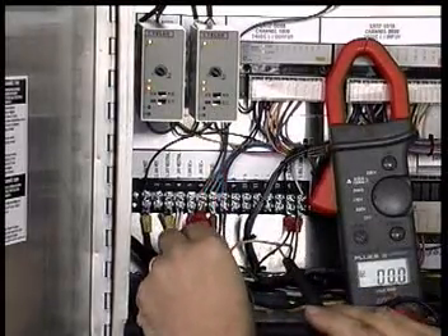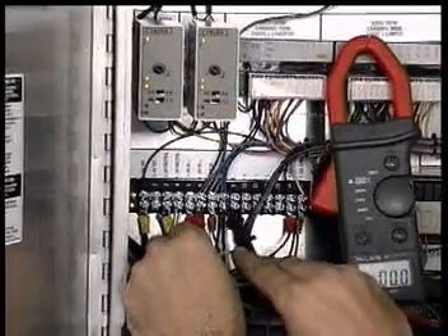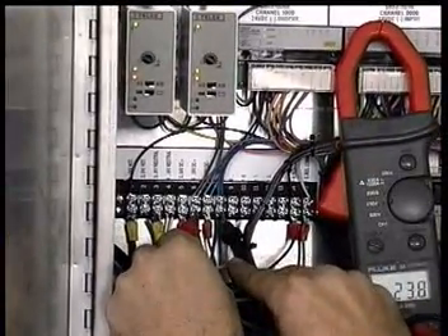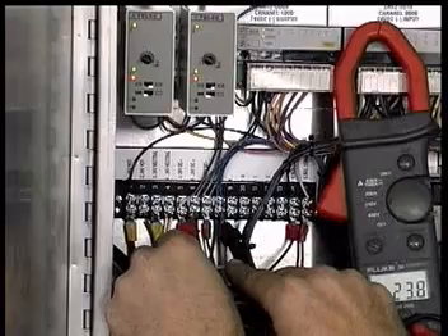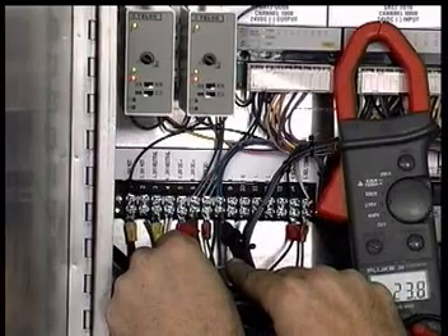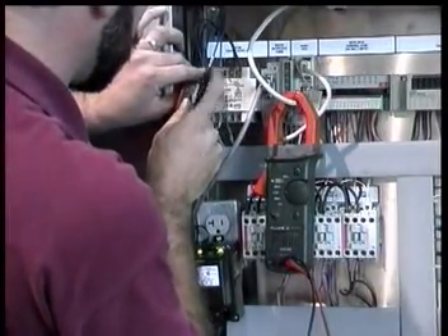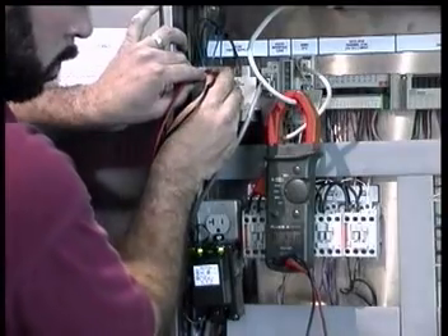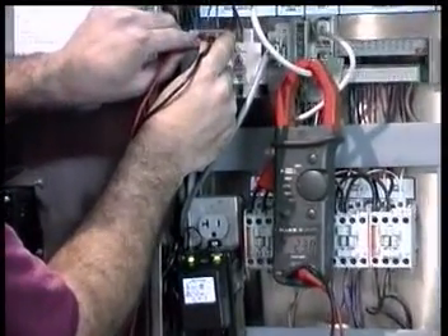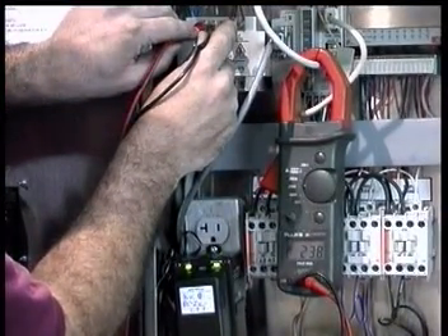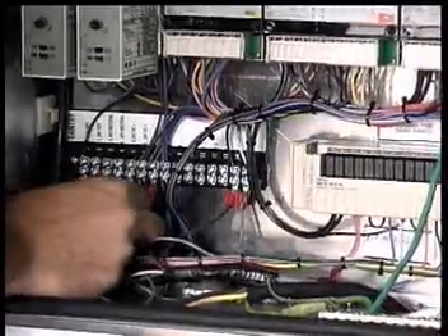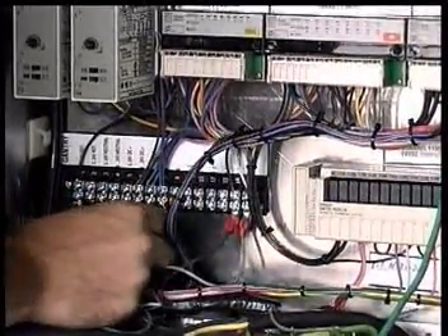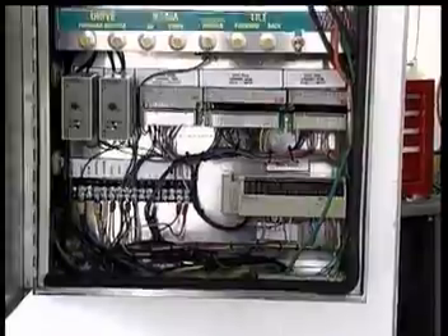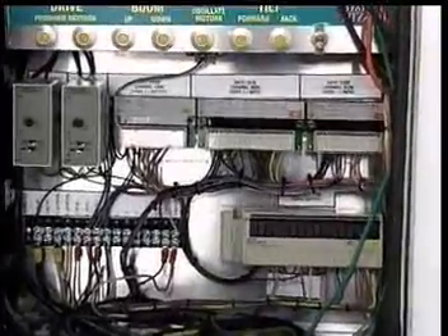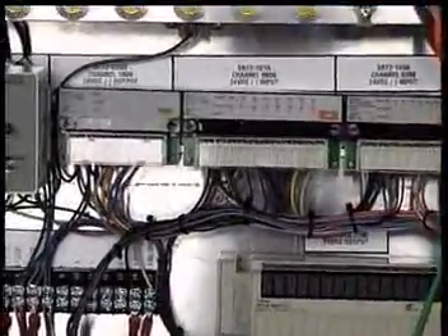If the power light is off, check for 24-volt DC power on the terminal strip and connections to the output cards. If power is not present at the terminal strip, check for 24-volt DC power at the power supply located in the control panel. If power is present at the supply and not at the gantry, check the 4-conductor gray cable and replace if necessary. If the communication lights are not lit, check the connections at the gantry terminal strip and the 4-conductor gray cable.